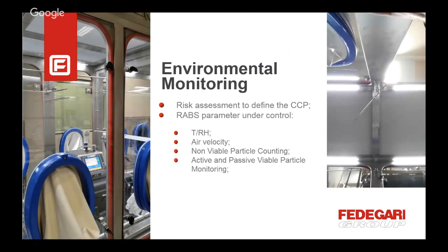All the RABS system is monitored. So we have decided, according to a risk assessment that helps to define the critical control points where the sampling needs to be located, and to keep the RABS under control. The parameters that we are measuring are temperature and relative humidity. For these two parameters we just take a reading, not controlling, because the control of temperature and relative humidity is provided by a centralized HVAC system of the background clean room.